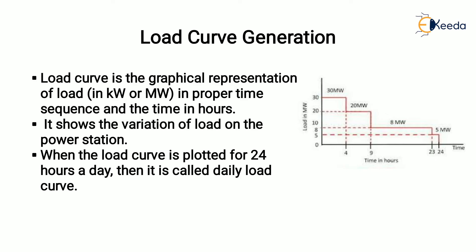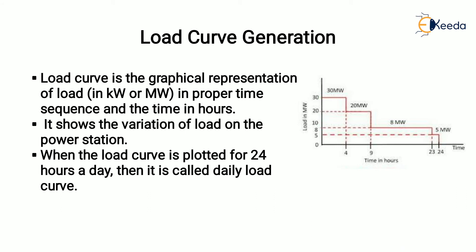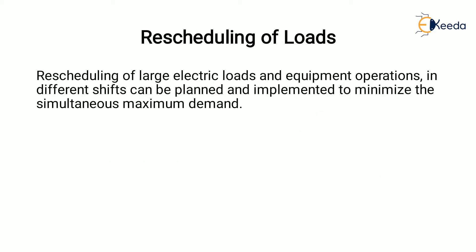The first step is load curve generation. A load curve is a graphical representation of consumer load demand against time in hours. As shown in the diagram, it shows the variation of load on the power station. When the load curve is plotted for 24 hours a day, it is called a daily load curve; similarly, we have monthly and yearly load curves. These curves are useful in predicting the patterns of peak and valley and energy use in industries or in a distribution network.